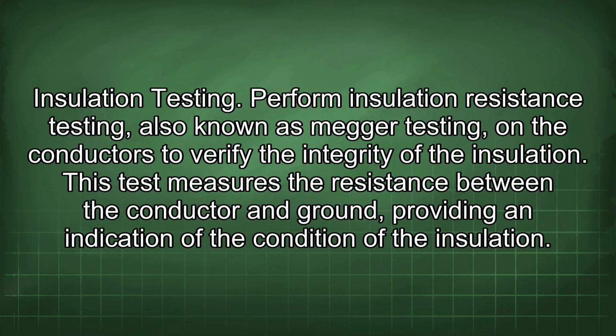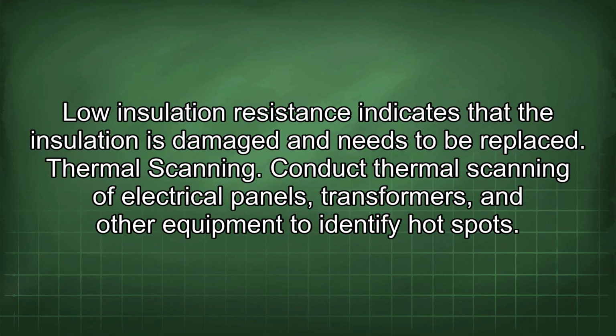Insulation testing. Perform insulation resistance testing, also known as Megger testing, on the conductors to verify the integrity of the insulation. This test measures the resistance between the conductor and ground, providing an indication of the condition of the insulation. Low insulation resistance indicates that the insulation is damaged and needs to be replaced.